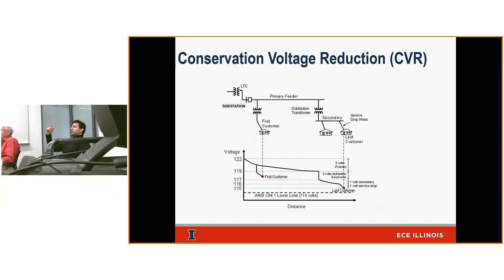Here's a figure — I used something similar when we talked about voltage drop calculations. This shows a typical feeder, borrowed from an EPRI report. It shows 122 volts at the feeder head. As you go away from the distribution substation, the voltage gets reduced. The 2- to 3-volt drop on the primary from 122 to 119 is mainly due to impedance on the lines and conductors.